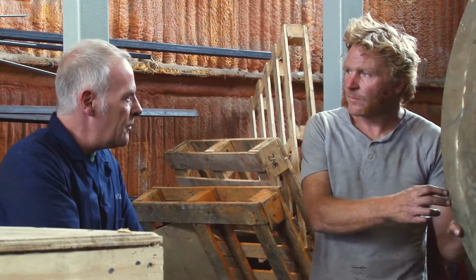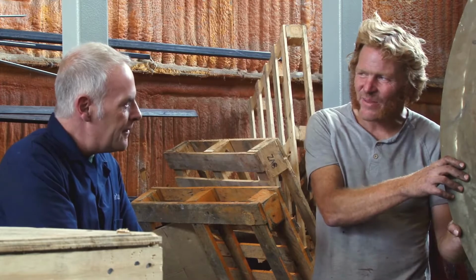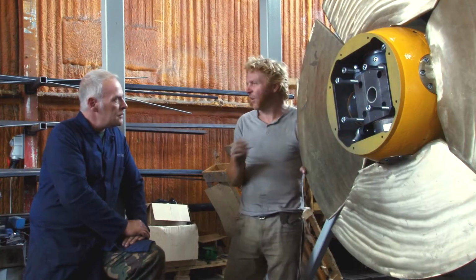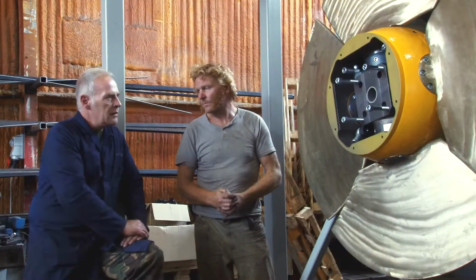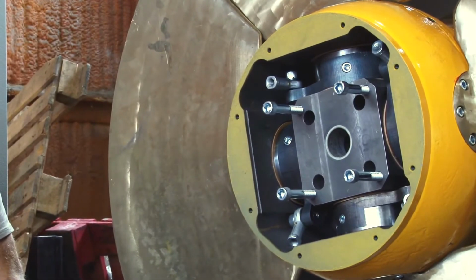If you look at the River Avon, virtually every mile and a half, there's a weir. Wherever there was a weir, going back to the Saxons, they used it for power. We seem to have forgotten how to do this. Which is a pity, isn't it? But this type of machine is ideally suited to that very low amount of fall, of head. It's the most efficient for low head sites. Like I say, this will run down to 80 litres a second and still maintain 80% efficiency at those low flows, with a peak efficiency of over 90%.